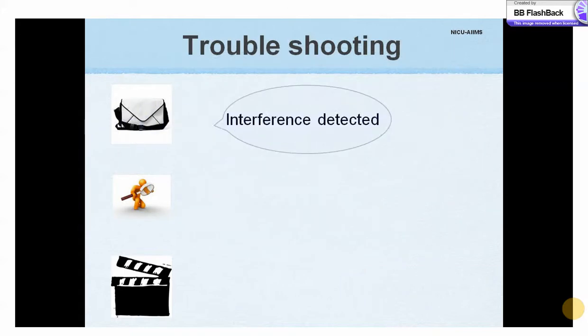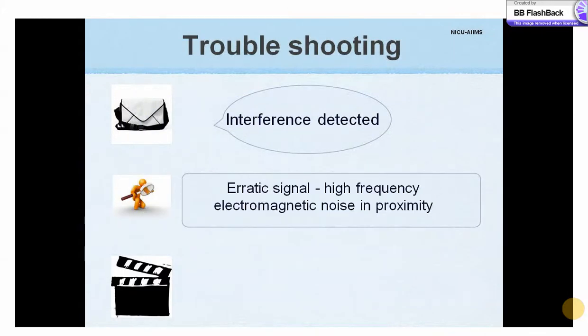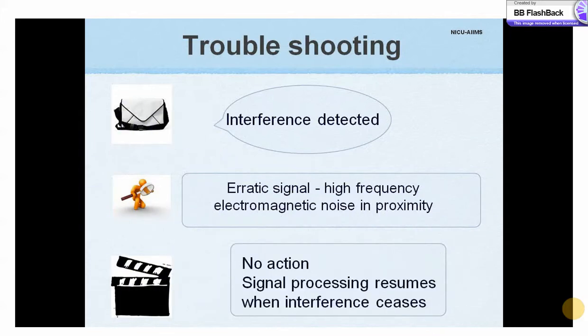If interference is detected, it means the signal is too erratic to be processed due to proximity of other electrical equipment generating high frequency electromagnetic waves. Generally, no action is required as the readings either do not change or become dashes if the interference persists. Signal processing resumes when the interference ceases.